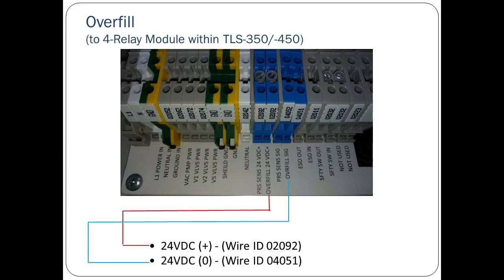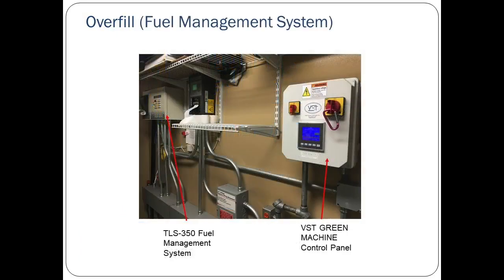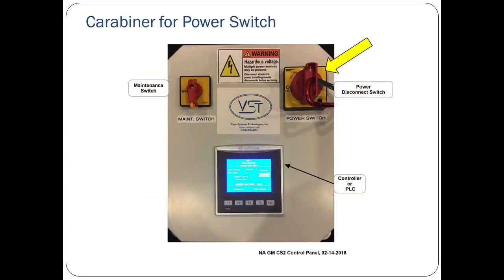The VST control panel, on the right, must be connected to a 4 relay module within the fuel management system, shown on the left. In this example, the tank monitoring system is a Veeder-Root TLS 350. Once all the wiring is complete, the VST control panel can be turned on by turning the power switch to the on position.